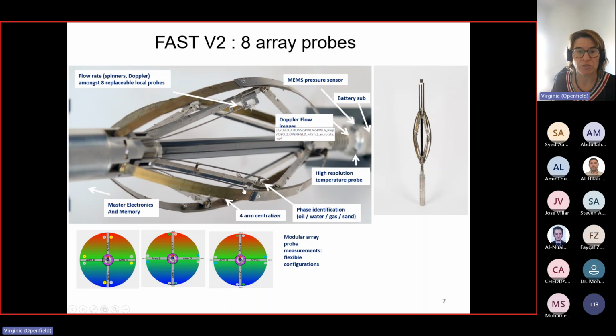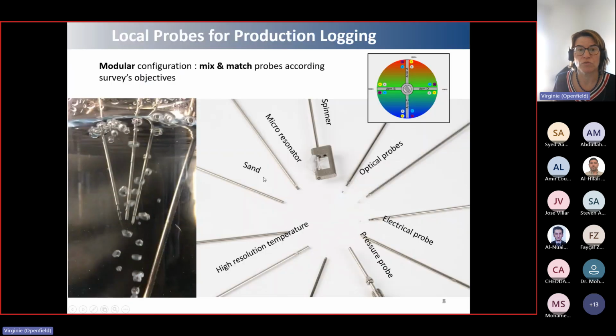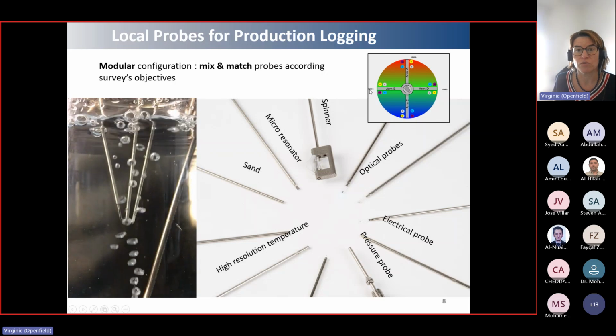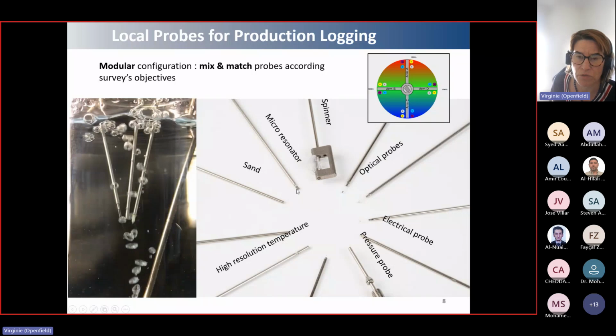But actually you can mix and match. You can remove these probes depending on the needs of the logging survey. That's shown in these cross sections, where, up to the client operator's logging objective, we can choose the best probe. For instance, if it's gas wells, we tend to use optical probes and spinners. If it's more an oil producer with water holdup as the main focus, we tend to use more electrical probes, whether it's conductivity or capacitance. So the important thing is the main tool body stays the same, and then you can change the probes based on the logging objective. These are local probes that we design and that we also sell individually.